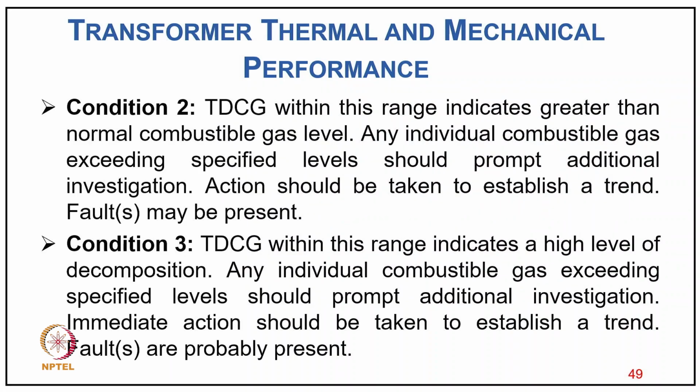prompt additional investigation. Now coming to condition 2, TDCG within the range indicates greater than normal combustible gas level. Any individual combustible gas exceeding specified levels should prompt additional investigation. Action should be taken to establish a trend. Typically, a fault may be present.